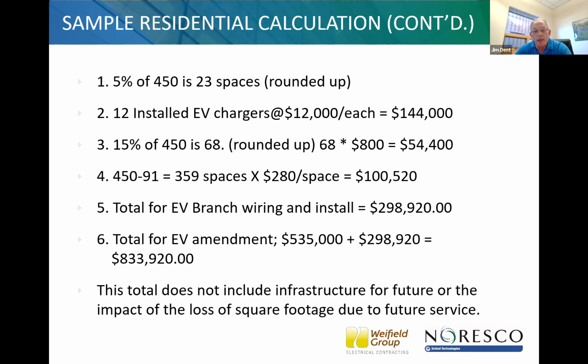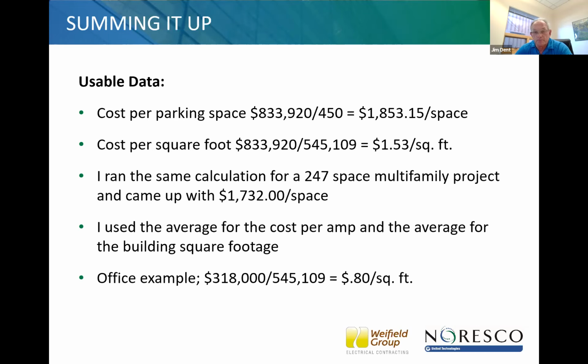So if you take the EV switchgear, $535,000, and the $298,000, you come up to $833,920. That doesn't include the infrastructure for future or the impact of the loss of square footage due to the future service. Next slide, Kev. $833,920 divided by 450 is $1,800 a space. And the cost per square foot for the facilities, both of them around 550,000 square feet, is $1.53 a square foot. Those are a couple of metrics you can use when you're looking at projects for yourself.